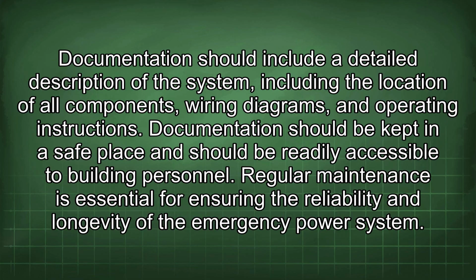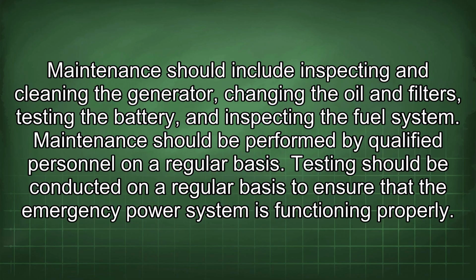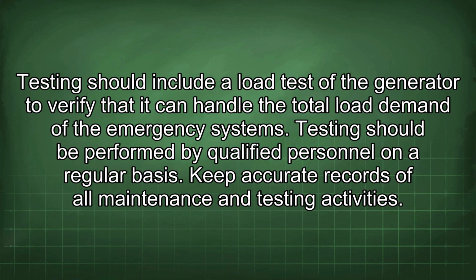Regular maintenance is essential for ensuring the reliability and longevity of the emergency power system. Maintenance should include inspecting and cleaning the generator, changing the oil and filters, testing the battery, and inspecting the fuel system. Maintenance should be performed by qualified personnel on a regular basis. Testing should be conducted on a regular basis to ensure that the emergency power system is functioning properly. Testing should include a load test of the generator to verify that it can handle the total load demand of the emergency systems. Testing should be performed by qualified personnel on a regular basis.